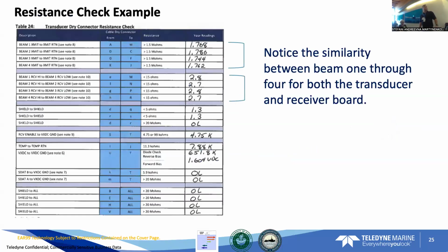Okay, and again, this is what the actual resistance check looks like whenever you're completing it. You notice that everything looks kind of the same. Nothing's crazy off sync here. You have your receive enable check here, and this one's actually important to know because it's either going to be 4.75 or 99 kilo ohms. Don't worry too much if that's kind of out of whack. If it's like 105 or so, that's fine. You want something close to the ballpark. It doesn't have to be exact.